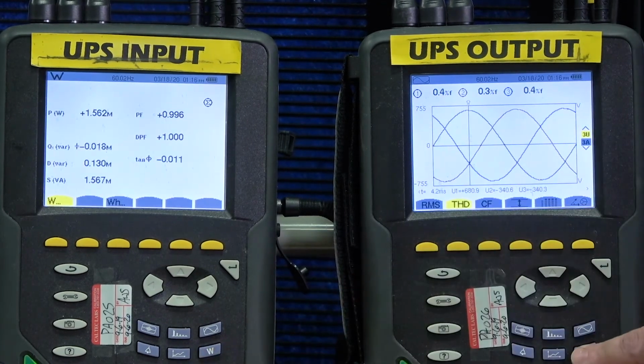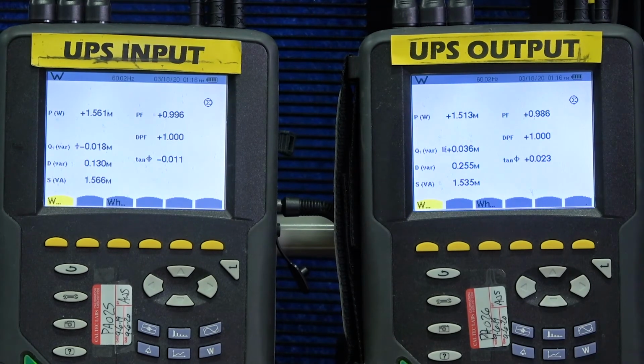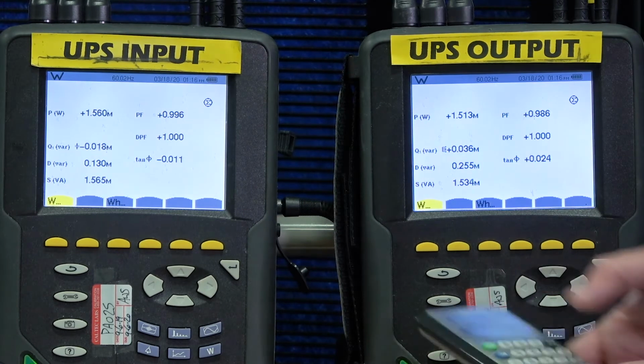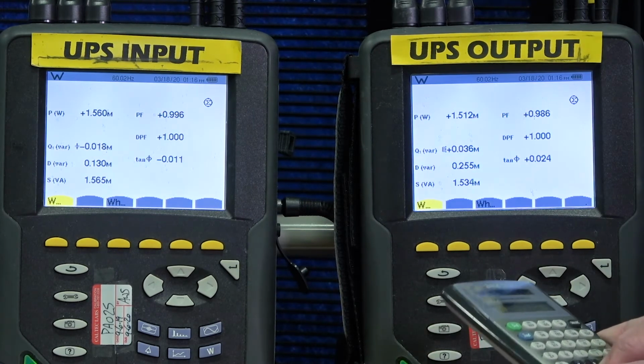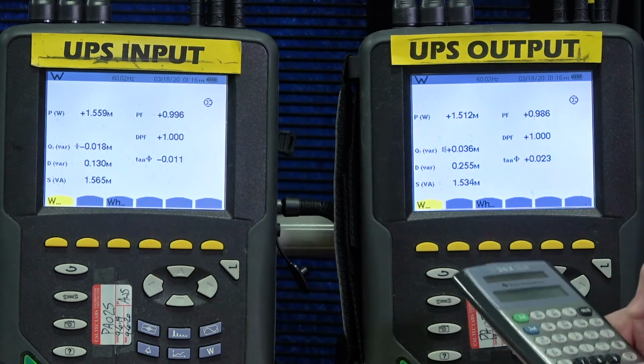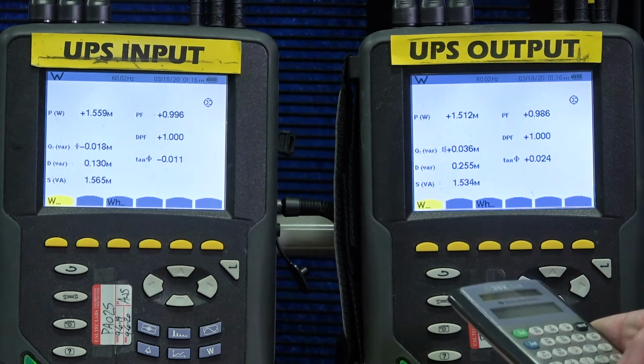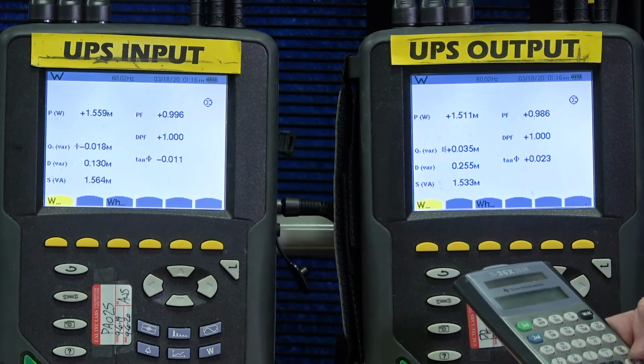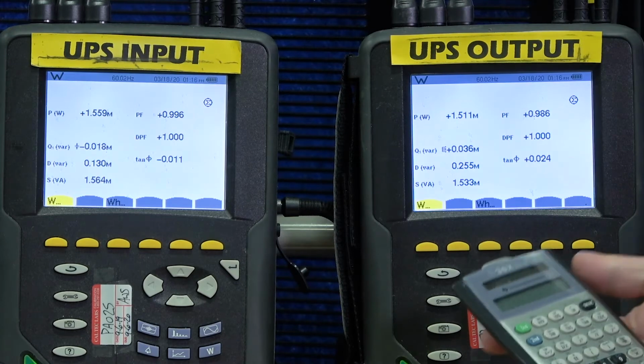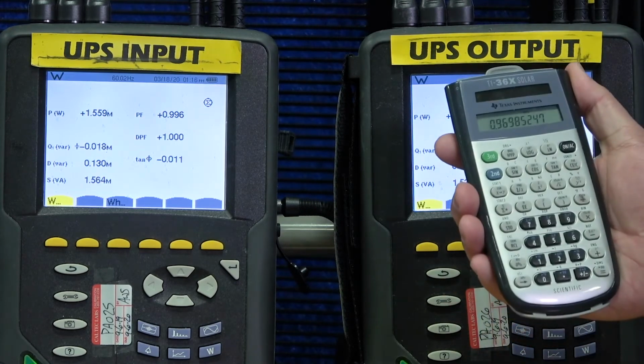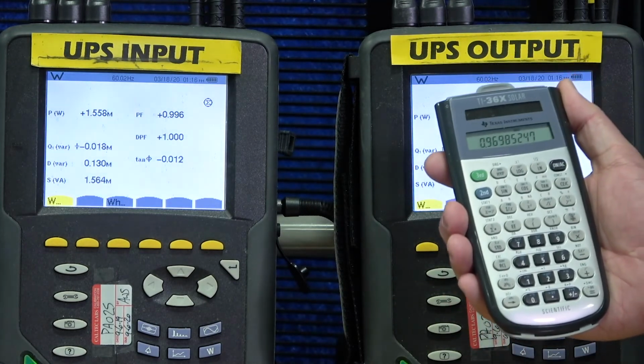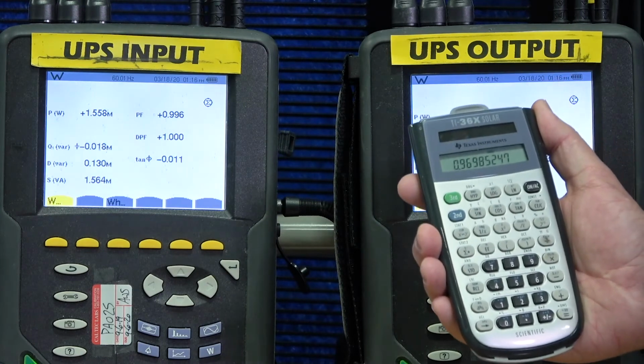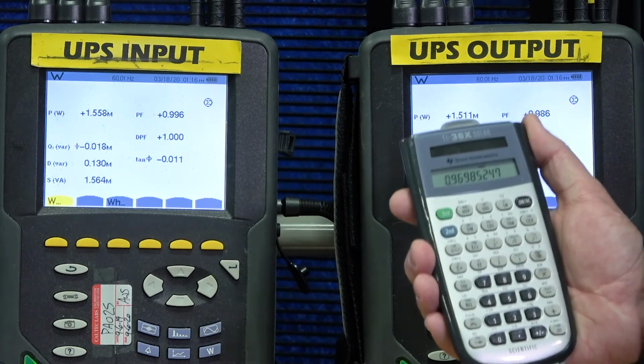Back to the output power on the UPS system. We're operating at 1.512 megawatts divided by 1.559 input megawatts for a total UPS efficiency of 96.98% or 97% UPS efficiency.